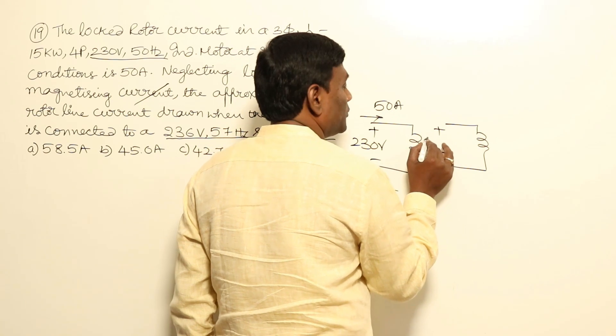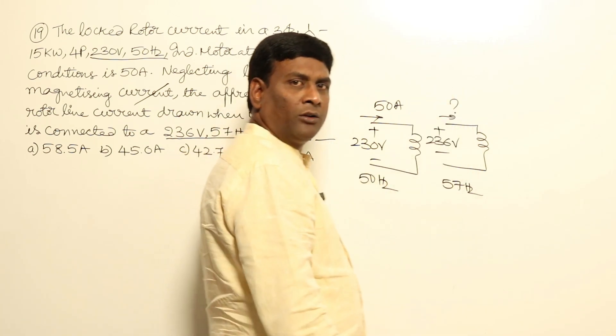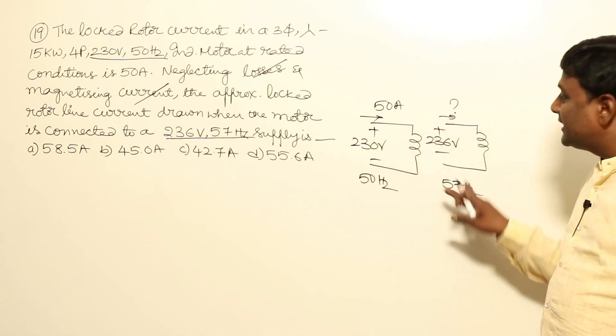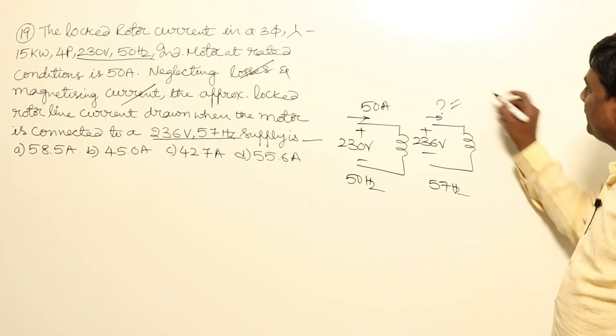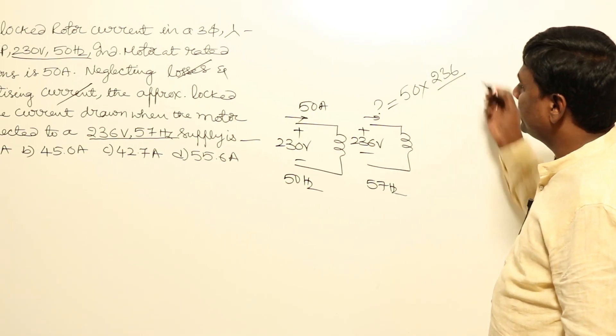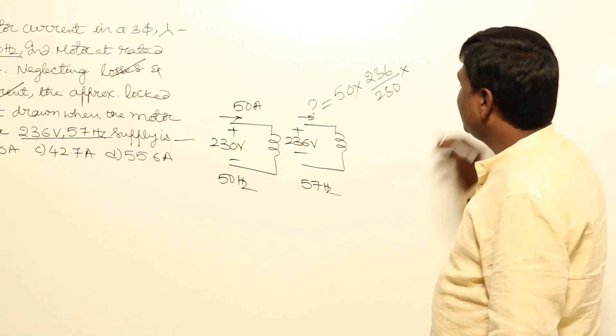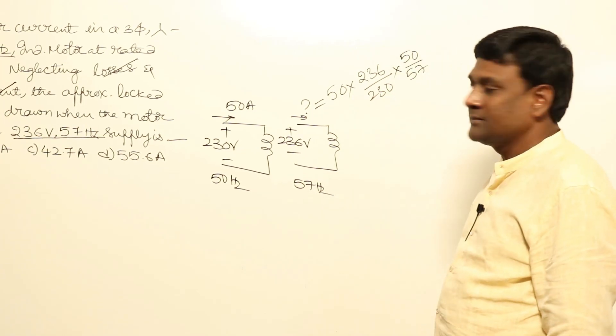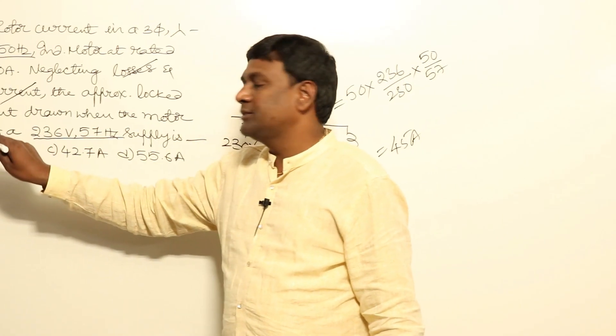At 236 V and 57 Hz, the locked rotor current changes as follows: if voltage increases, current increases; if frequency increases, reactance increases and current decreases. So the new current = 50 × (236/230) × (50/57) = 45 amperes. The answer is 45 amperes.